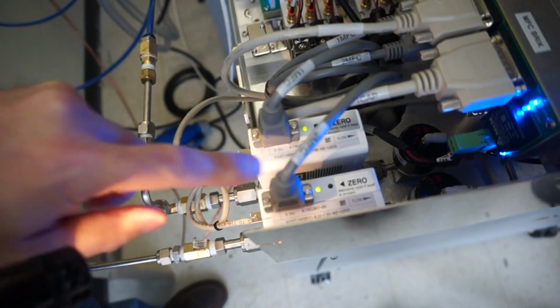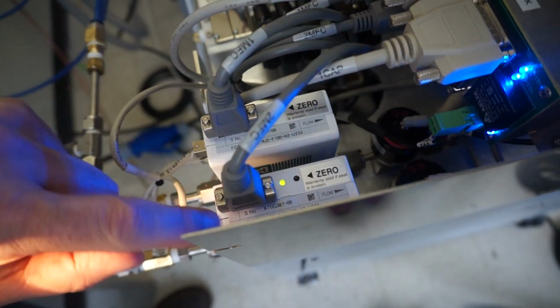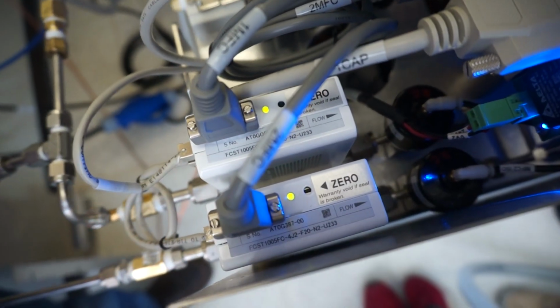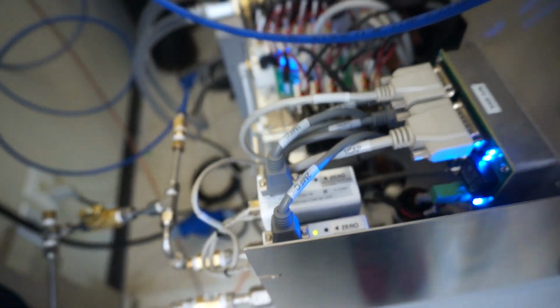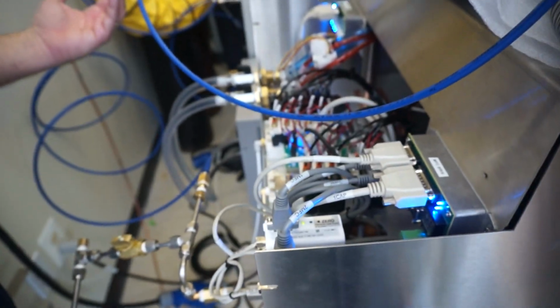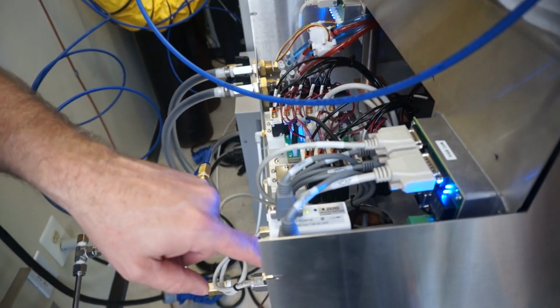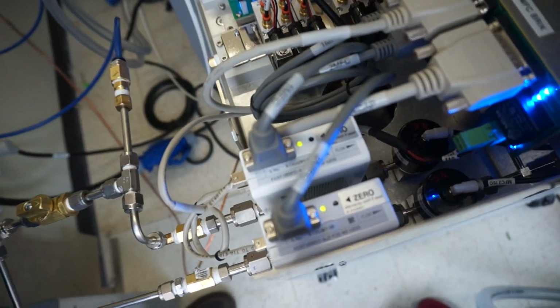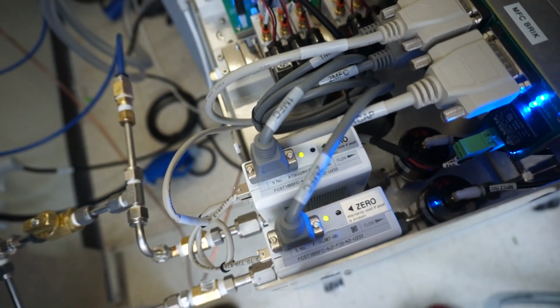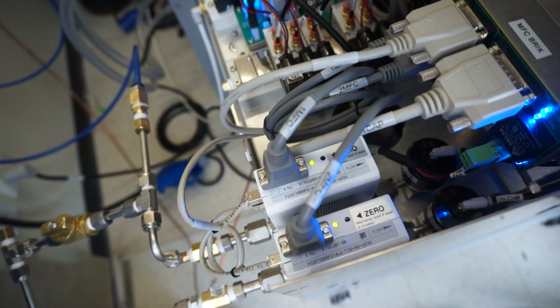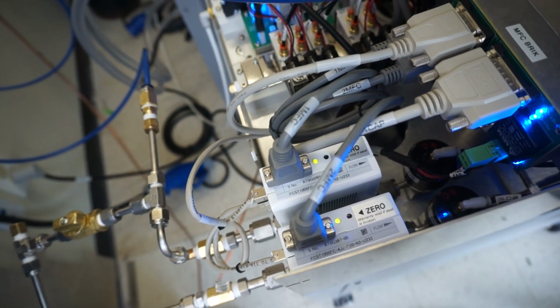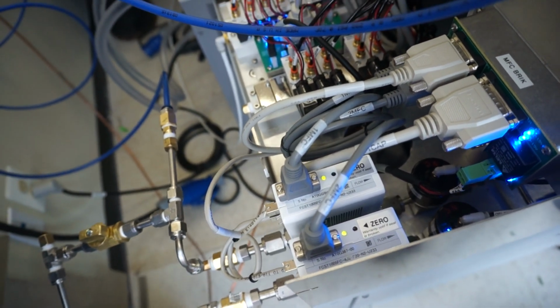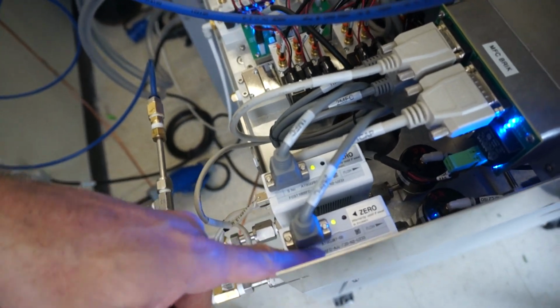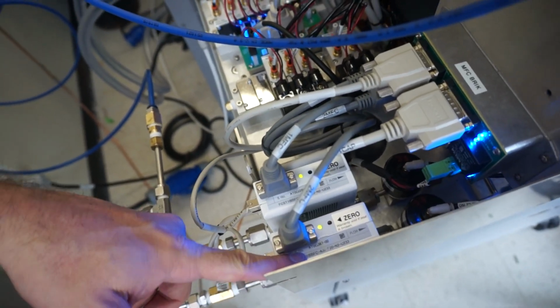If you look at the flow controllers, it says F100 and F20. So what that is: F100 is a 100 sccm mass flow controller. That's the master controller. And F20 is a 20 sccm. It's a slave controller. So if you're doing metal, if you're doing oxides or nitrides, you always want to first run off your first mass flow controller, and then bleed in a small amount of nitrogen or oxygen on the second one. And I'll show you how to operate that via recipe.